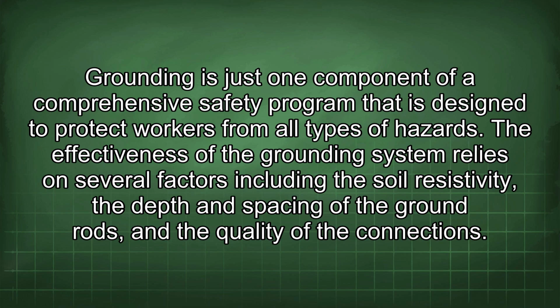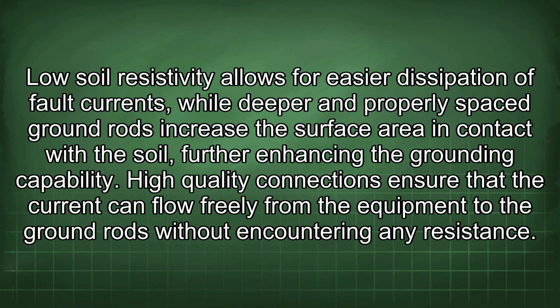Grounding is just one component of a comprehensive safety program that is designed to protect workers from all types of hazards. The effectiveness of the grounding system relies on several factors, including the soil resistivity, the depth and spacing of the ground rods, and the quality of the connections. Low soil resistivity allows for easier dissipation of fault currents, while deeper and properly spaced ground rods increase the surface area in contact with the soil, further enhancing the grounding capability. High-quality connections ensure that the current can flow freely from the equipment to the ground rods without encountering any resistance.